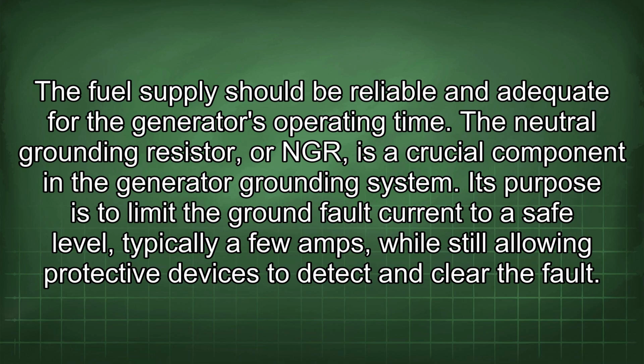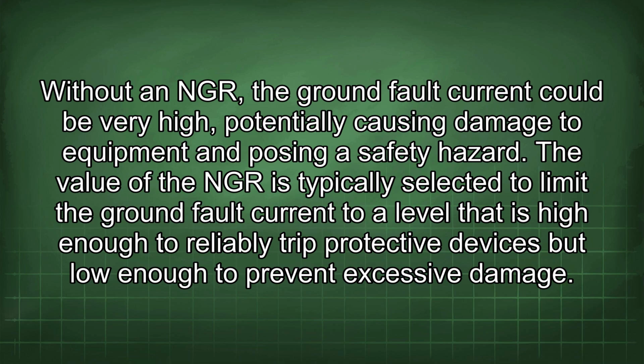The neutral grounding resistor, or NGR, is a crucial component in the generator grounding system. Its purpose is to limit the ground fault current to a safe level, typically a few amps, while still allowing protective devices to detect and clear the fault. Without an NGR, the ground fault current could be very high, potentially causing damage to equipment and posing a safety hazard. The value of the NGR is typically selected to limit the ground fault current to a level that is high enough to reliably trip protective devices but low enough to prevent excessive damage.